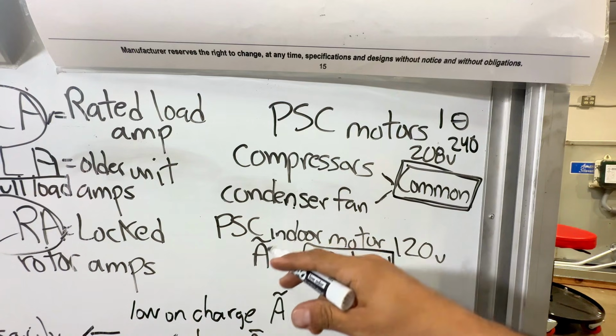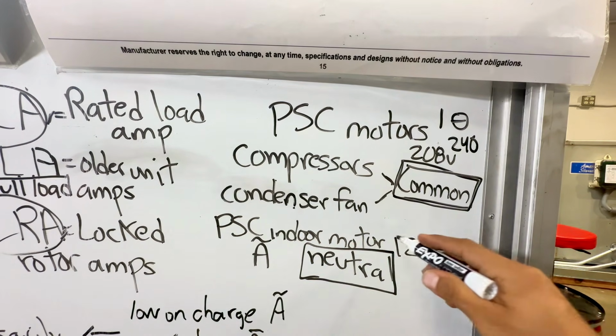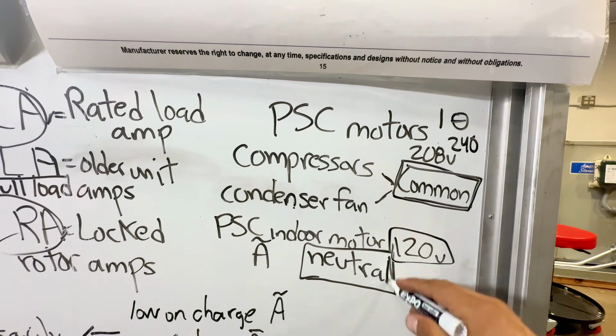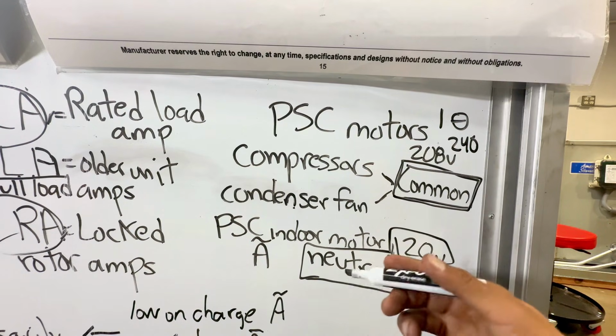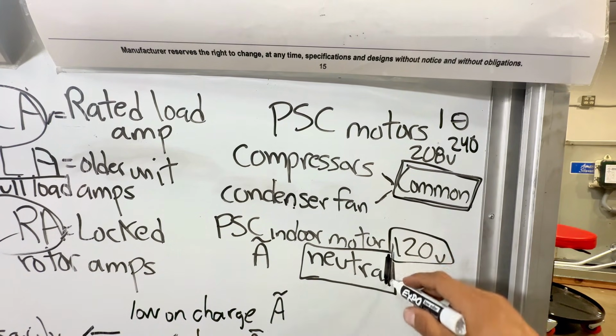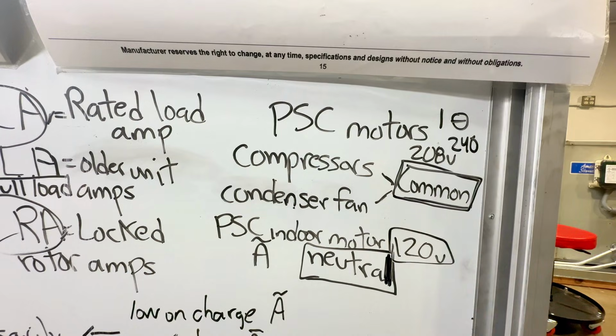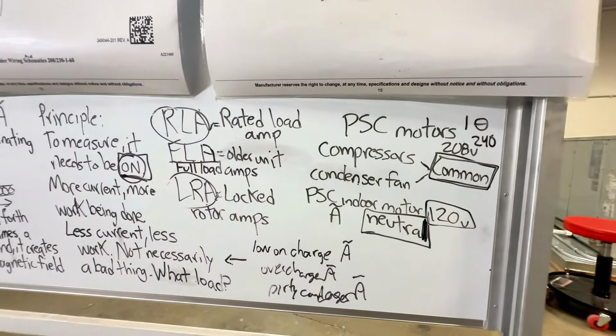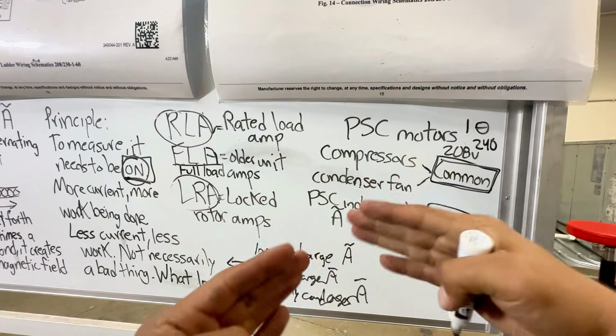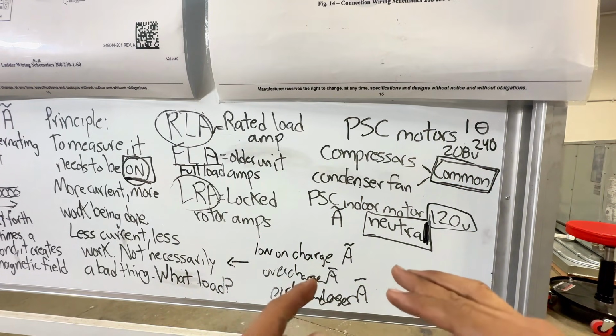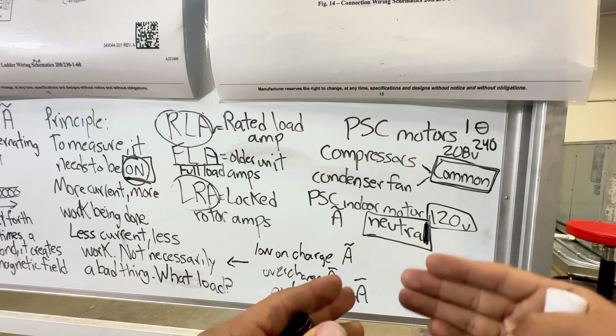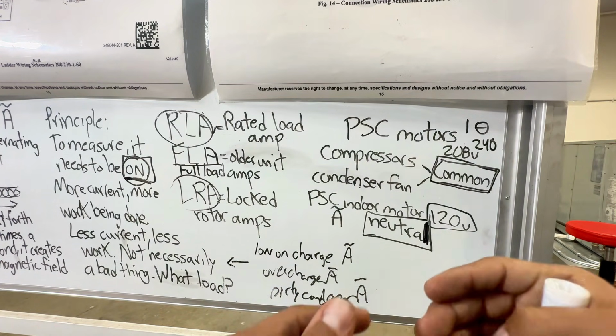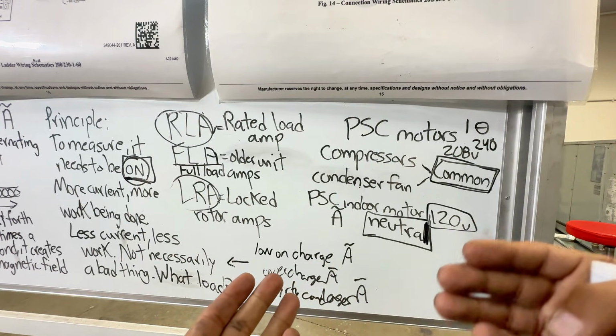So if you're dealing with the PSC indoor motor that's 120 volts, then you would check your neutral, right? Not so much your speed, but you would check your neutral. All right, so now we're gonna go to the unit, and I'm gonna show you examples of different loads and the current. You're gonna see how I can manipulate the compressor so it can change the current, and that can give you an idea, because that basically is a symptom of something possibly not working correctly.